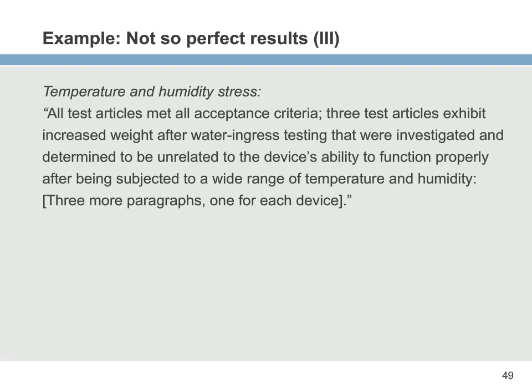All test articles met the acceptance criteria for temperature and humidity stress. 3 test articles exhibited increasing weight after water ingress. They were investigated, determined to be unrelated to the device's ability to function properly after being subjected to a wide range of temperature and humidity. So, again, the test report said that.